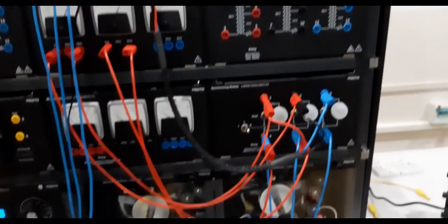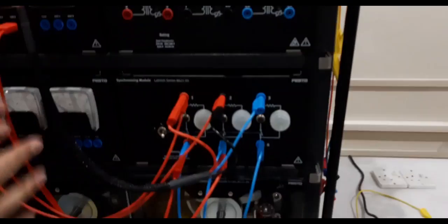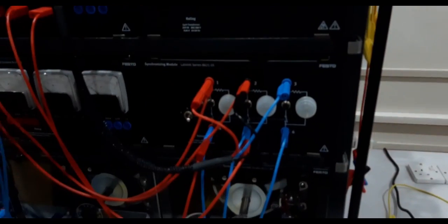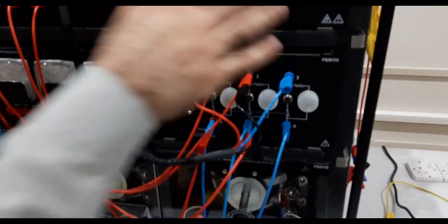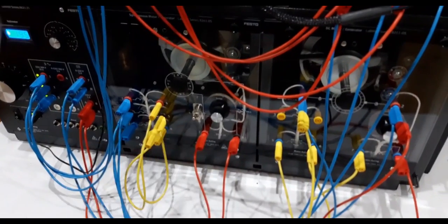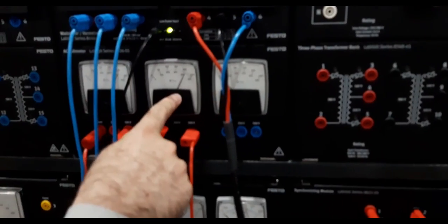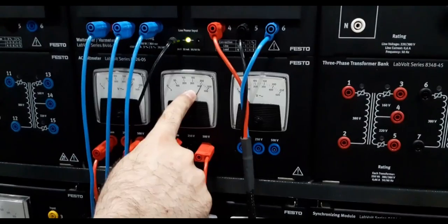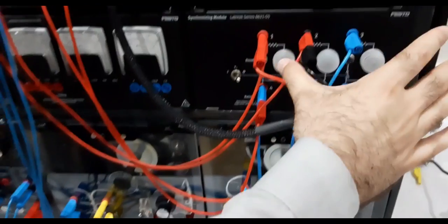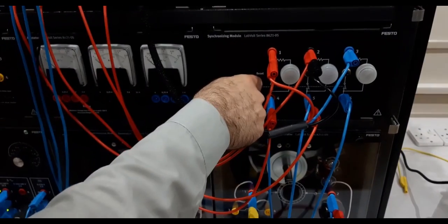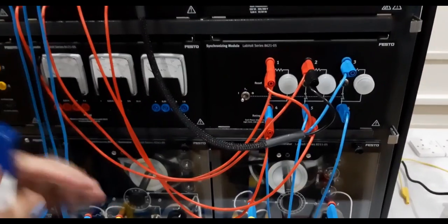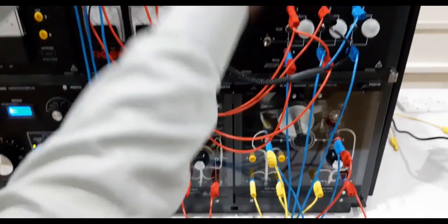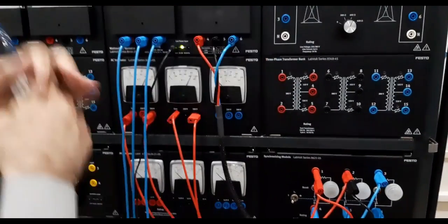Yes. So now you see that before synchronization, before connecting the generator to the WAPDA, by increasing or decreasing the field, the magnitude of the induced EMF and correspondingly that of the terminal voltage changes. So now there is no blinking and we can turn the switch on. So now this synchronous generator is synchronized with the system.